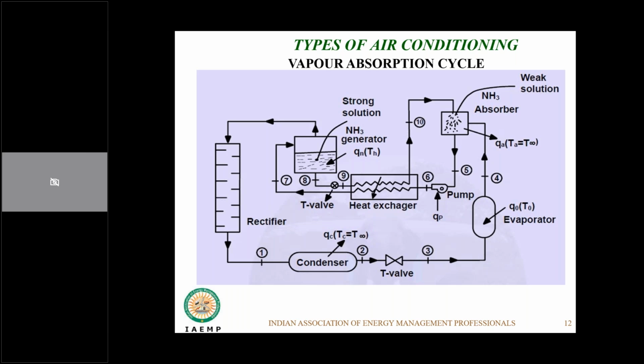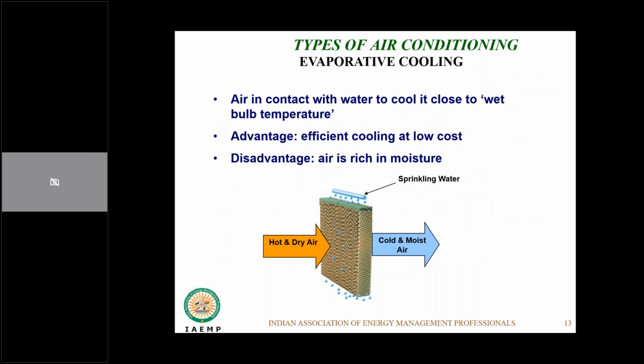This system is very effective in a scenario where you have a lot of waste energy available. The COP of this is almost three times lower; it requires three times more energy than a vapor compression system, because it's not very efficient in that sense. But if you have waste heat available, like solar energy that you're dumping out somewhere, you can use that for heating the solution here in the generator, and also in the heat transfer here. And then you have a cooling tower. You need a cooling tower to reject the heat out. It will become much more efficient, because you're not paying for this energy.